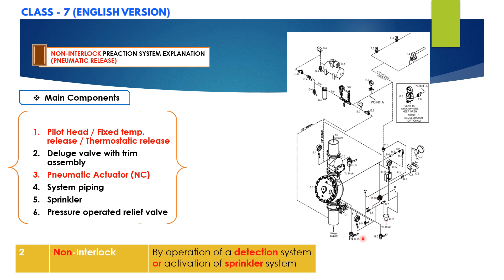Apart from this, as noted earlier, you will also require an air compressor, pressure switches, alarm bells, and pressure gauges for proper functioning of the system. In short, pneumatically controlled pre-action systems require a pneumatic release system equipped with thermostatic rate-of-rise release, fixed temperature release, or pilot heads. The release trim utilizes a pneumatic actuator held closed by pressure maintained in both the pneumatic release system and the closed sprinkler piping.